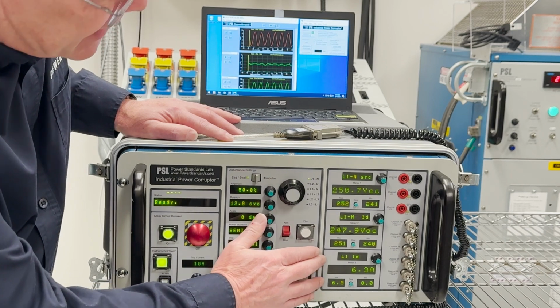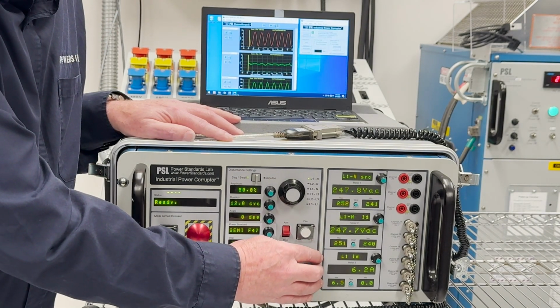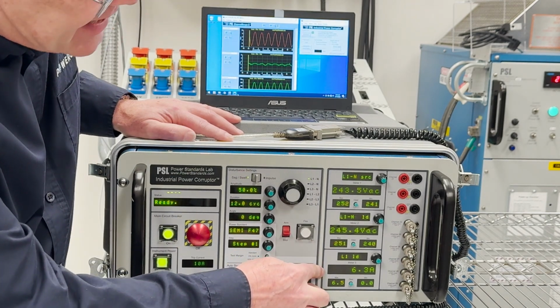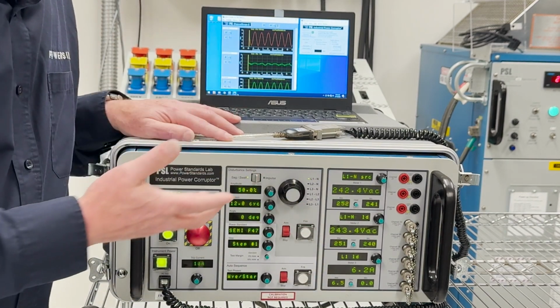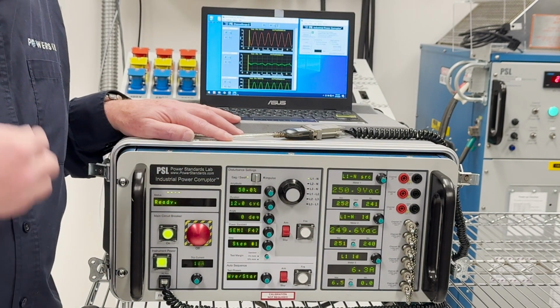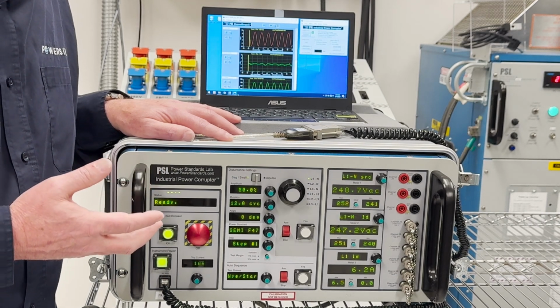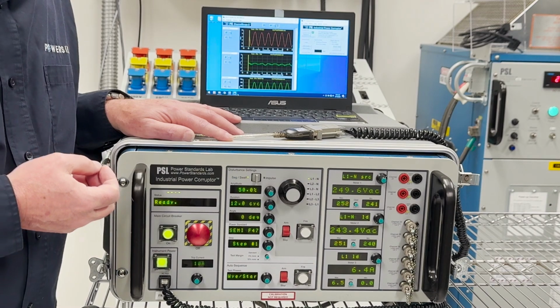And here on the line 1 load, this is the nominal current of the equipment under test. So you can see we have around 6 amps here. That is what we're drawing. We've got a resistive load, so we're not expecting any major inrush or any major disturbance to the process, but we don't know, right? We don't necessarily know all the characteristics.